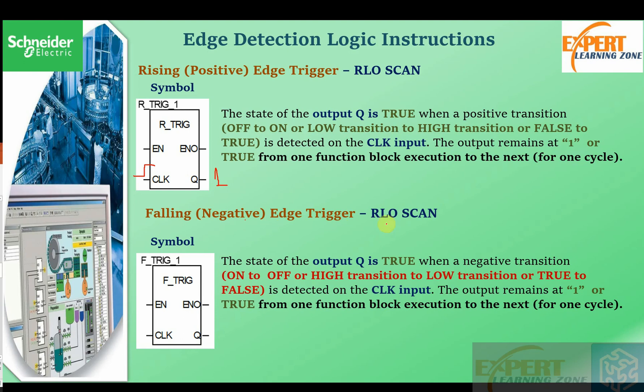Next is the falling or negative edge trigger, which is the direct opposite of the rising edge trigger. The state of the output is true when a negative transition — on to off, high to low, or true to false — is detected on the clock input. The output remains at one for one function block execution, that is one cycle. If there is a change in the clock signal from logic one to logic zero, the output becomes one for one clock cycle. You can assemble all the logic on the left side of the block to evaluate the change.